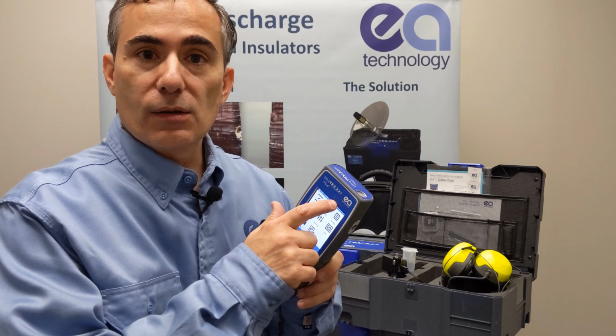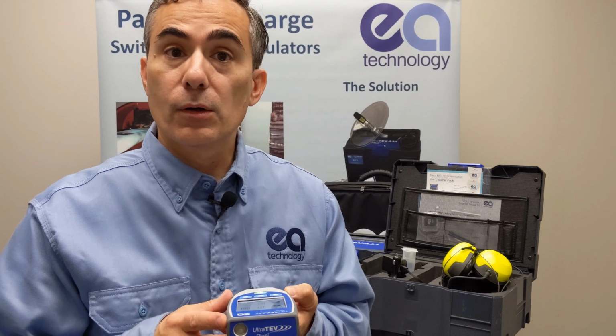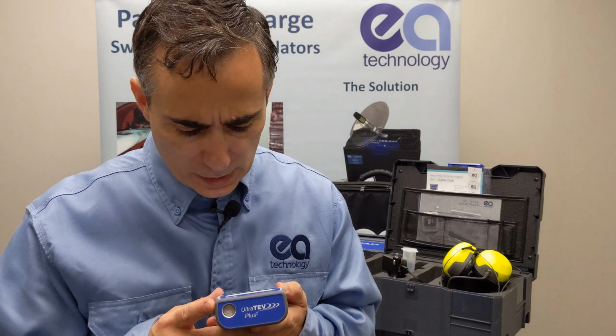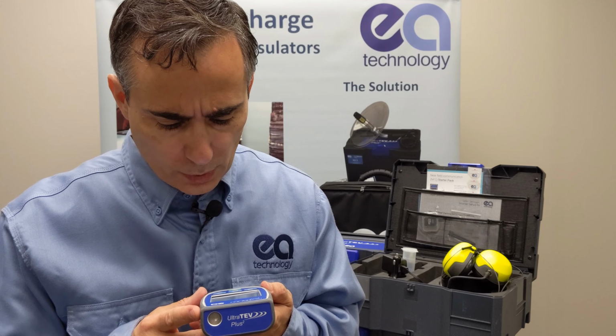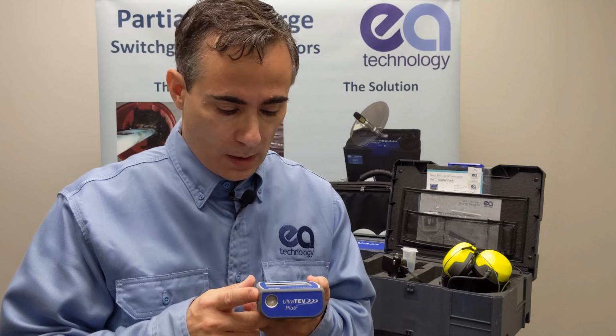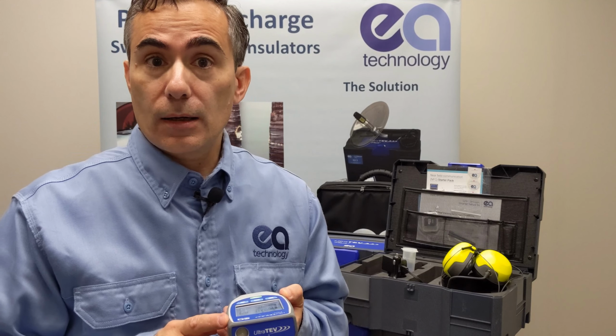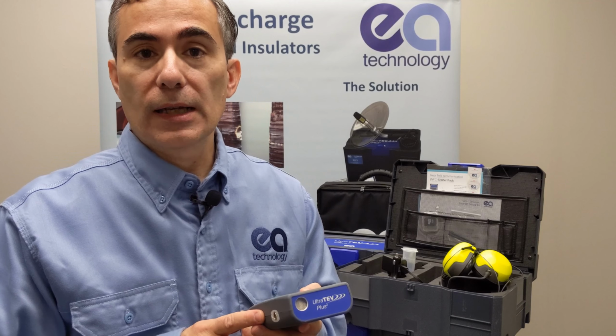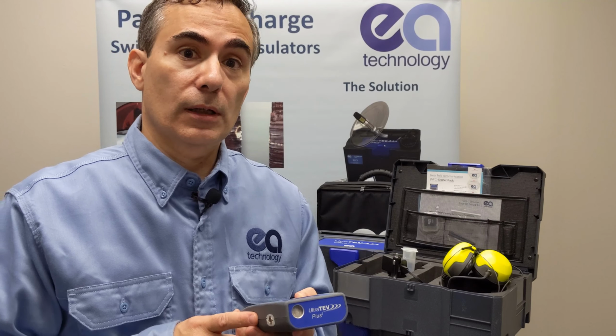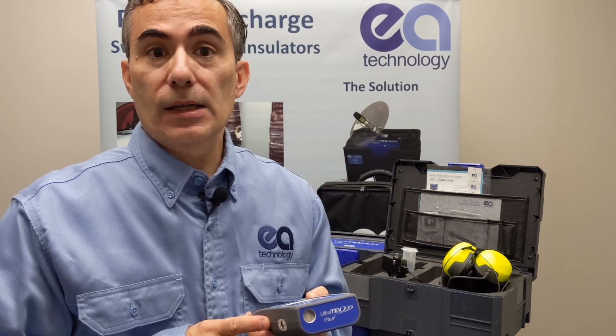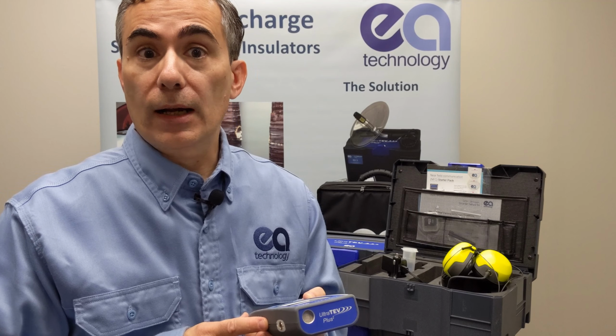Just above the display is a photo sensor to determine the phase frequency. Based on our fluorescent lighting here, we have 59.99 Hertz. If you're not able to get a lock that way, there's a built-in E-field sensor as well, and ultimately you could enter it manually. It's important so that your plots come out correctly.